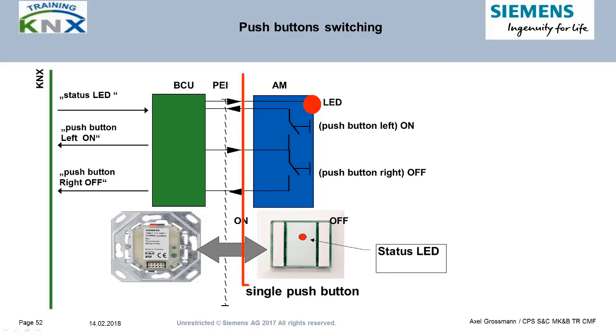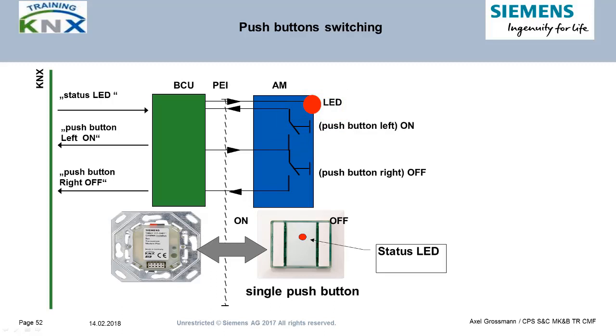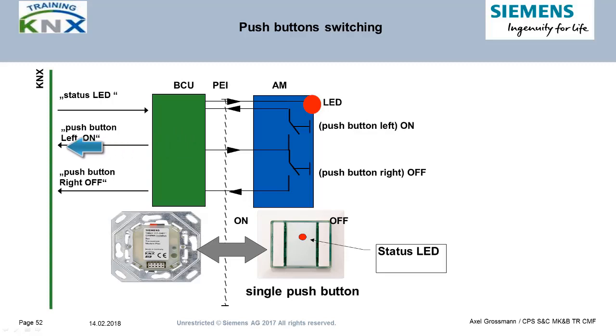Starting from the right side: we have the application module with two push buttons and one LED. When you press one of the buttons, you close an electrical contact and change the voltage on one of the signal pins on the PEI. The bus coupler registers this change and starts the program routine assigned to it. If the left button is pressed, a telegram with the user signal value of 1 is sent to the bus; with the right button, the opposite value 0. You will also learn in detail how the complete telegram looks.